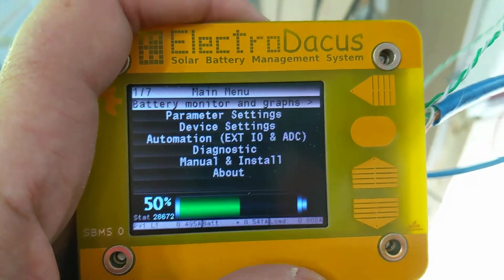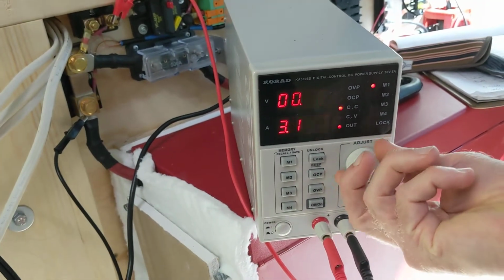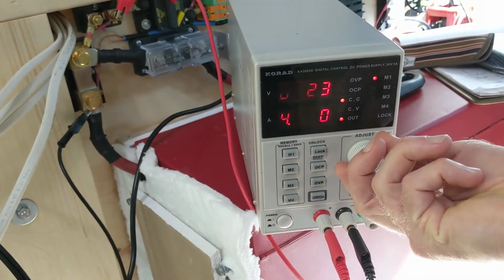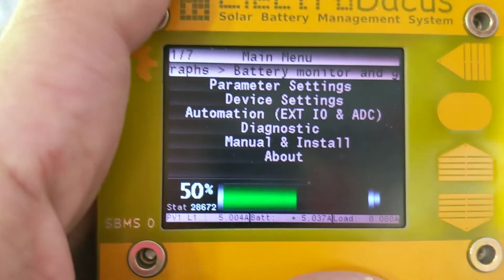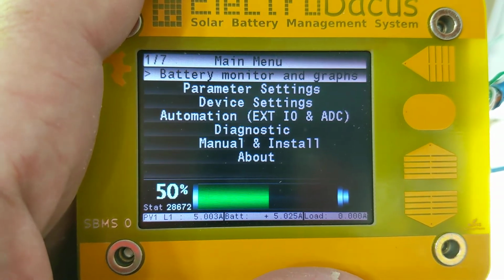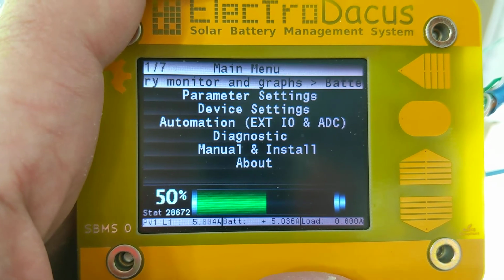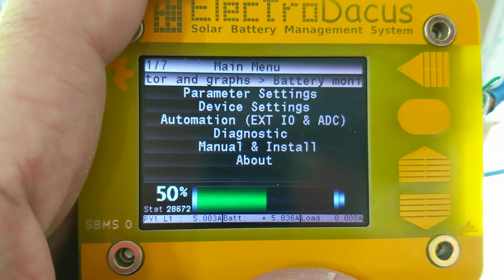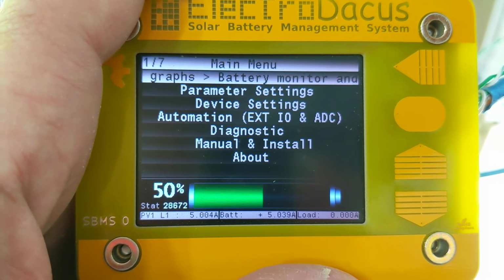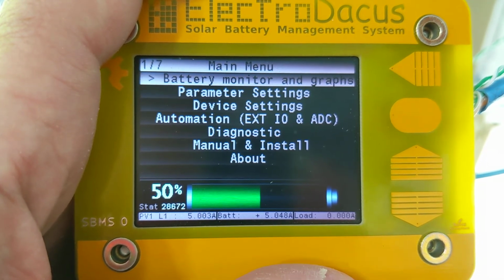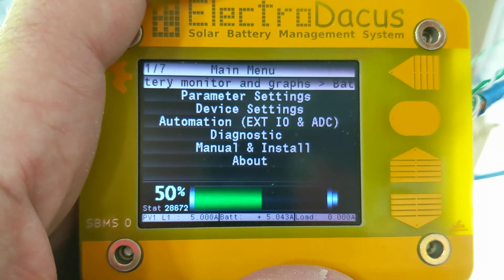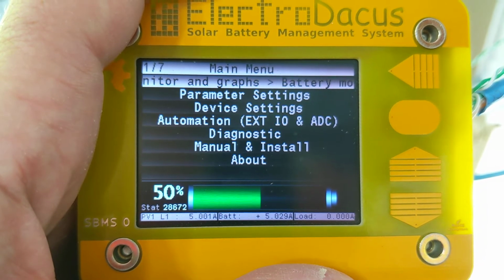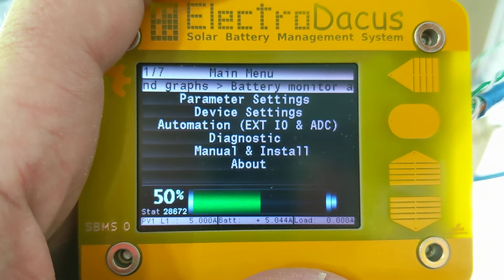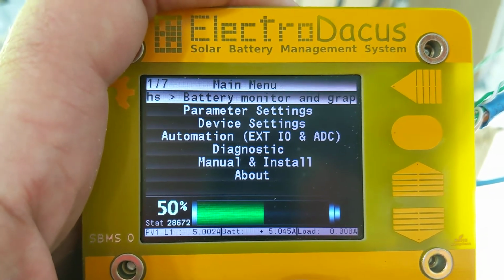So I'm going to increase the current to 5 amps running through the power supply. Again, we can see that the solar panel shunt is reading fairly accurately within about 0.1%. But the battery shunt is again, on average, reading 30 to 40 milliamps too high.